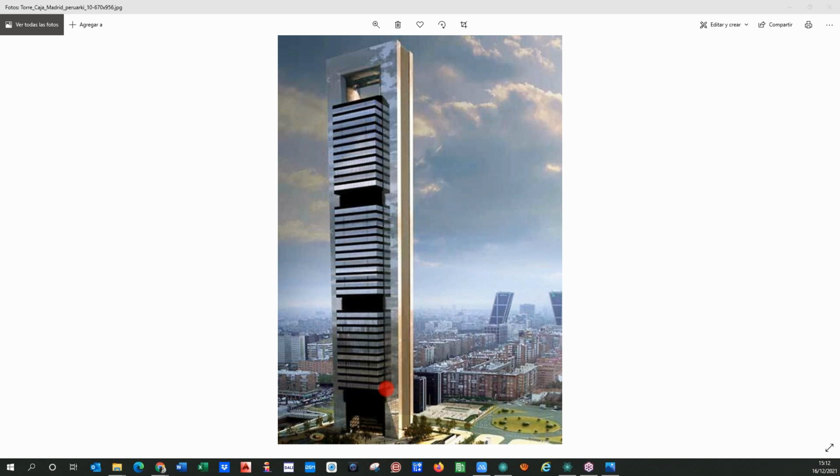So the first decision, I convinced the integrator also, and I convinced the end customer, the owner of the building, to change this to 68 IP routers. This was critical. And it was very easy to convince them because they wanted to solve the situation. The only devices that were changed was that. So the shutter actuators and the DALI gateways that are now 12 years old are still there working, because the problem was not with KNX.